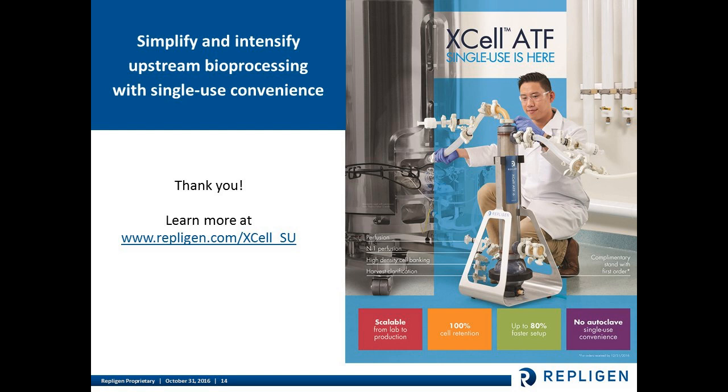Question: Can the XCell ATF single-use system be used in the same applications as the XCell ATF stainless steel system? Absolutely, because there has been no change to the hollow fiber membranes or the ATF pump design. The single-use units offer the same performance as the stainless steel units, so they can be used in cell retention applications such as high-density cell banking, N-1 seed train optimization, perfusion cell culture, and harvest clarification typically associated with fed-batch culture.